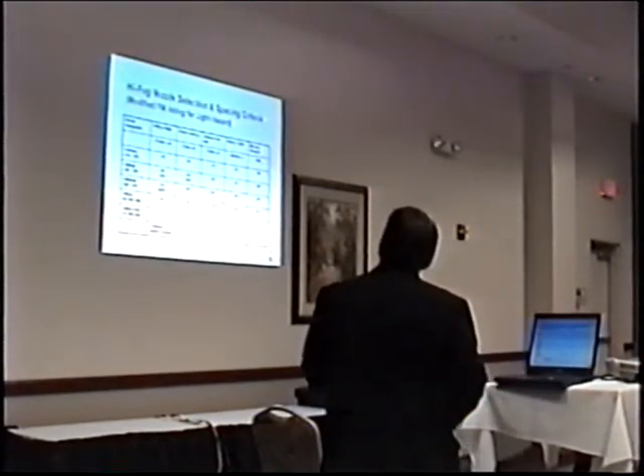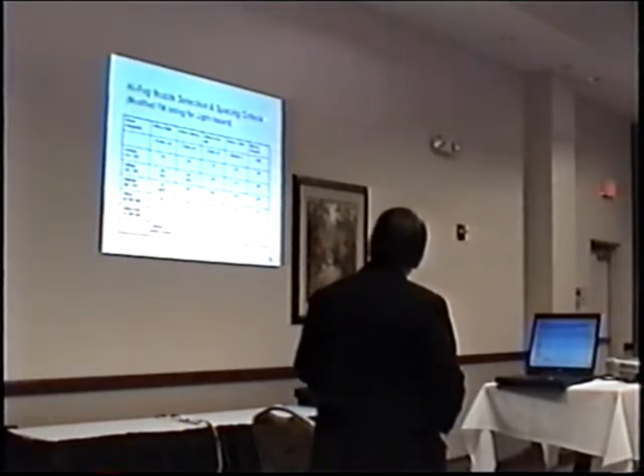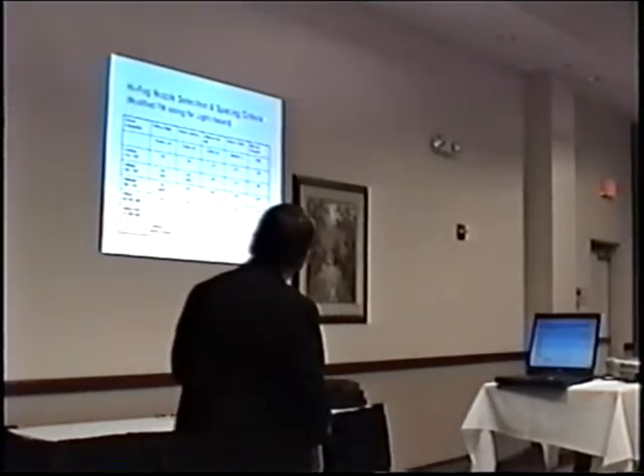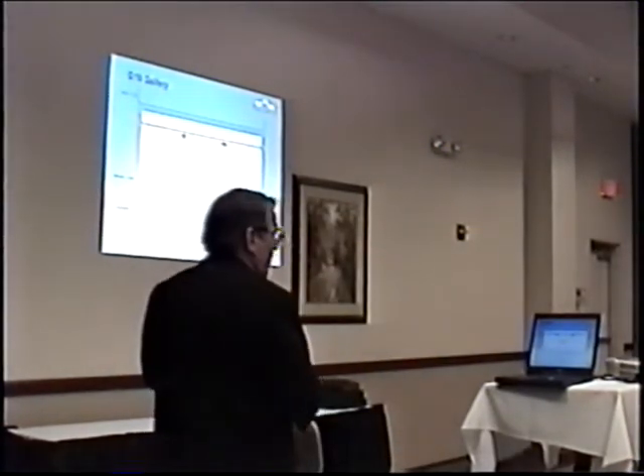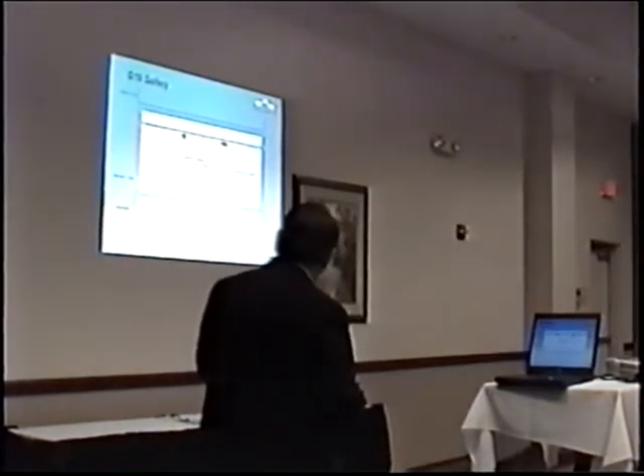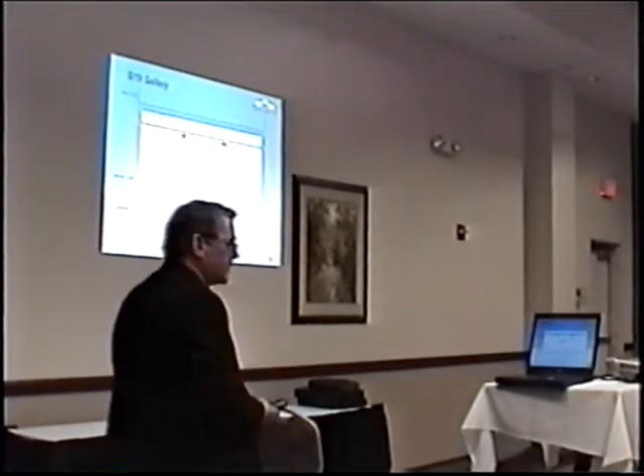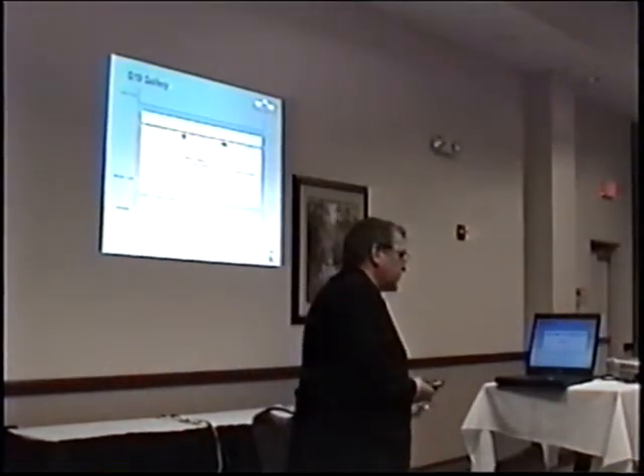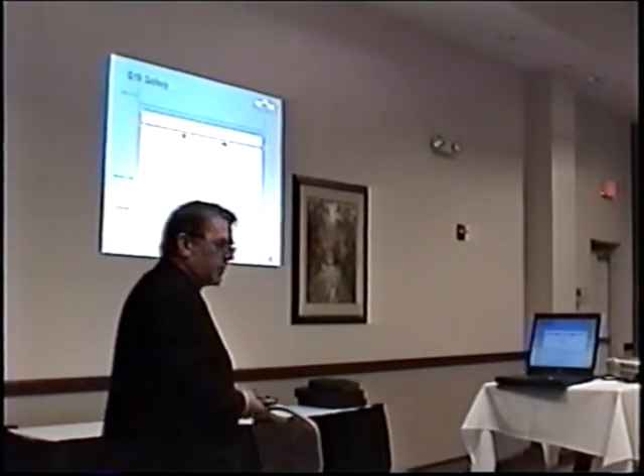Now the spacing is set by the listing, and distances from walls are defined, and the K factor in metric units is all established. So I had some nozzles to select from. But of course, nozzles tested for water mist systems are generally dealing with the standard tests, which are some kind of furnishings on the floor. There's one with furnishings in the corner. There's one with furnishings in the corner with the combustible wall panels. There's nothing anywhere to test for combustible ceiling. In fact, they all essentially are based on non-combustible ceilings.